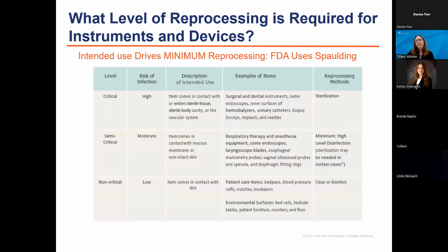So, what level of reprocessing is required for instruments or devices? FDA follows Spaulding classification. CMS also follows Spaulding classification. So, the intended use drives the minimum reprocessing. For critical procedures, so items that come into contact or enter sterile tissues, sterile body cavities, or the vascular system, they require sterilization. Semi-critical items that come into contact with mucous membranes or non-intact skin require at minimum high-level disinfection. Although some things in the dental world or in gynecology might only provide instructions for sterilization, right? So as long as it supersedes the minimum requirement, that's okay. And non-critical items that are intended to come into contact with only intact skin require cleaning and low or intermediate level disinfection.